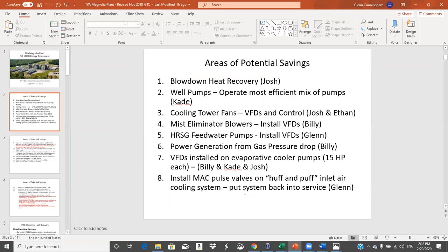TVA didn't use them. I don't know how we got onto this. We didn't know a lot about huff and puff filters when we got up there. But that pulsing of the filter is controlled by what they call pulse valves. And a pulse valve just fires. They probably had a 2 to 3 inch compressed air line going to a manifold, and those valves would fire, pss, pss, pss, pss, or go into a cleaning cycle. And it would pulse and knock the crap off of the inlet filters, which would keep down the pressure drop, which then helps the efficiency of the gas turbine.